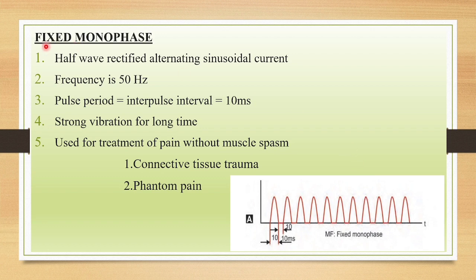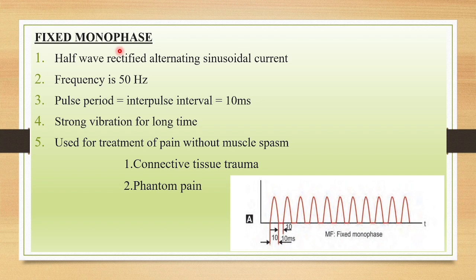The first mode is fixed monophase. In this, you will have half wave rectification, and the frequency will be 50 Hz. The pulse period is equal to the interpulse interval, that is 10 milliseconds — so 10 milliseconds ON to 10 milliseconds OFF. This mode produces stronger vibration for a prolonged period of time and can be used for treating pain without muscle spasm, for cases like connective tissue trauma or phantom limb pain.